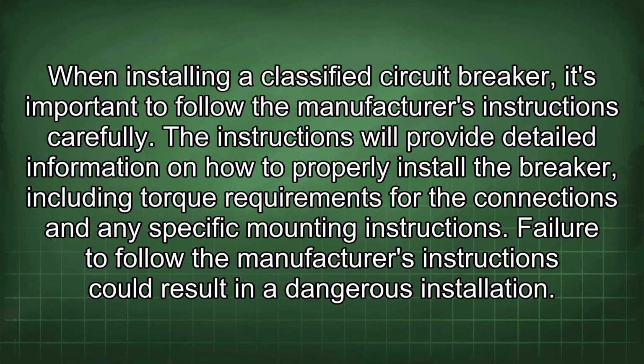When installing a classified circuit breaker, it's important to follow the manufacturer's instructions carefully. The instructions will provide detailed information on how to properly install the breaker, including torque requirements for the connections and any specific mounting instructions. Failure to follow the manufacturer's instructions could result in a dangerous installation.